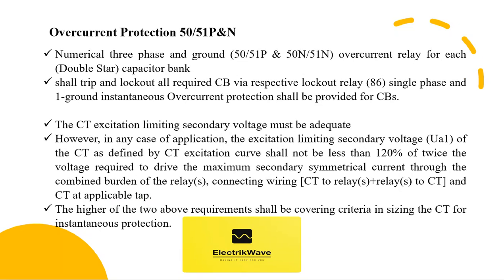Overcurrent protection shall include one numerical three phase and ground overcurrent relay for each double star capacitor bank. These protections shall trip and lock out all required circuit breakers via respective lockout relay. Single phase and single ground instantaneous overcurrent protection shall be provided for circuit breakers. The current transformer excitation limiting secondary voltage must be adequate such that the relay must be able to definitely operate.